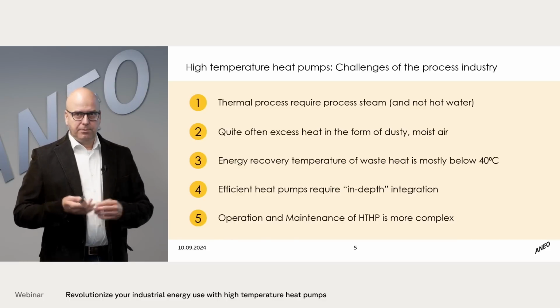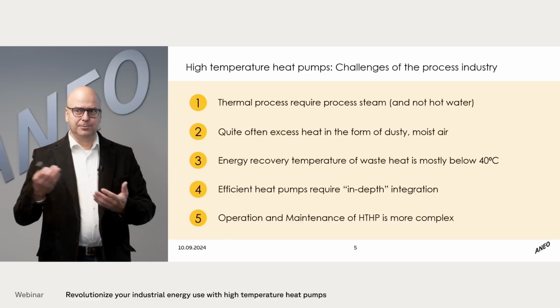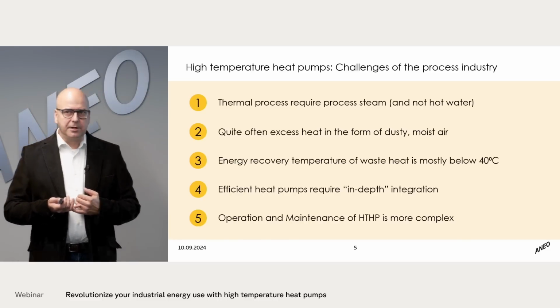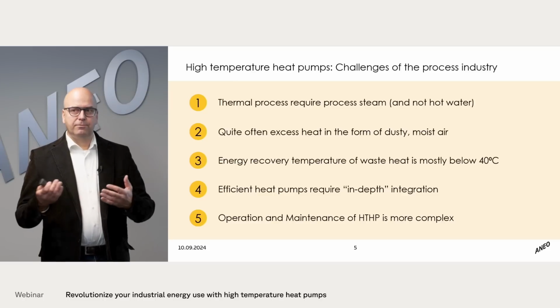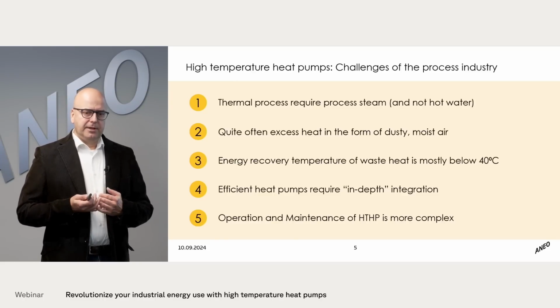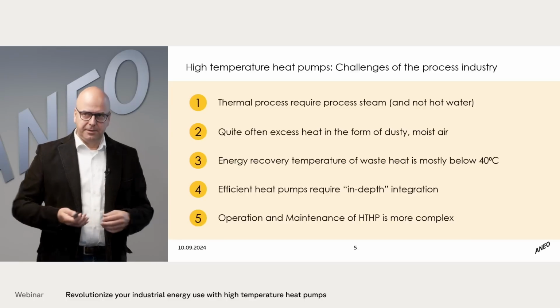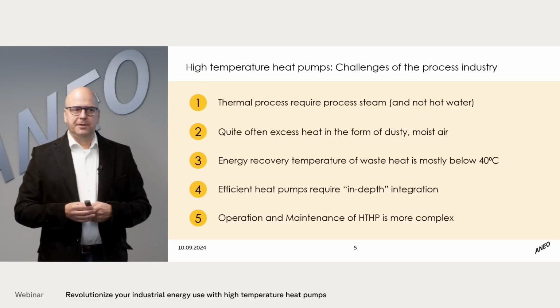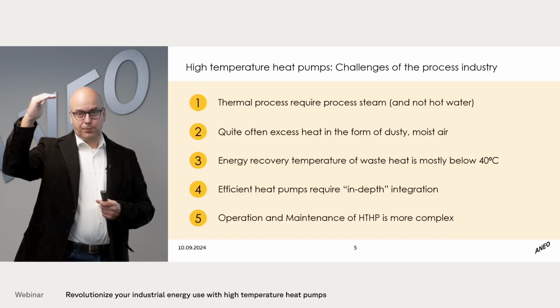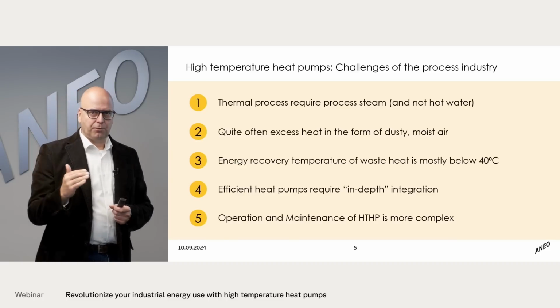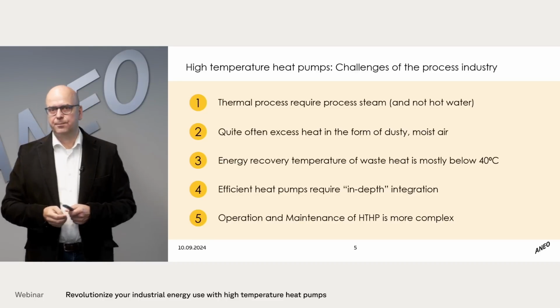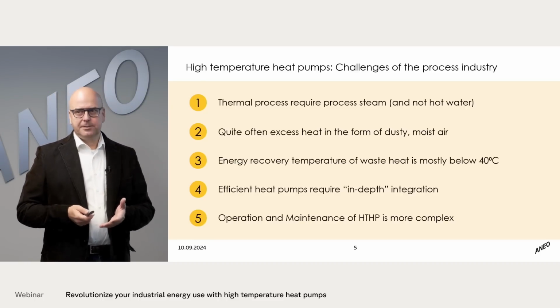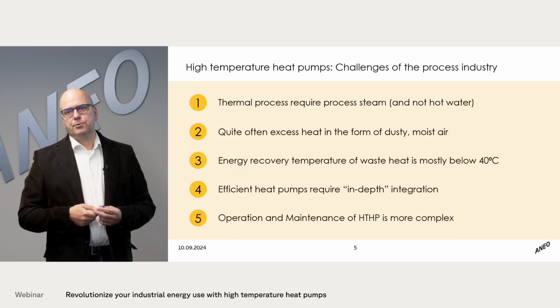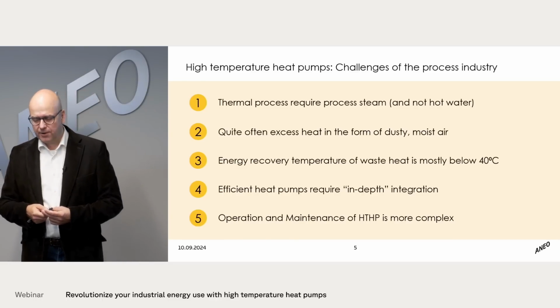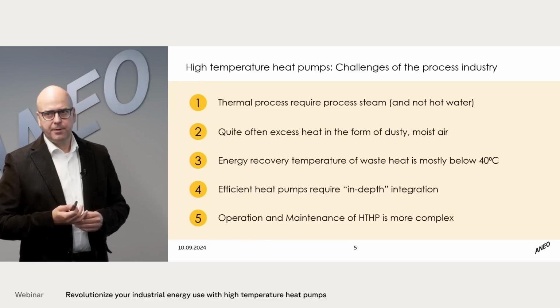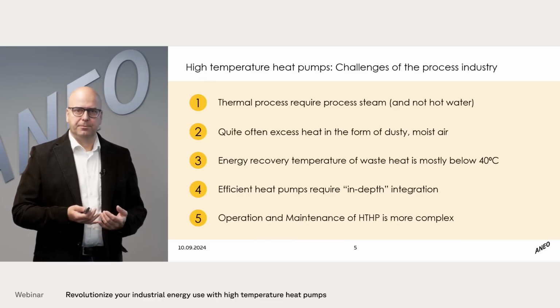By doing this setup, recovering excess heat, especially when it's sensible as well as latent, we see that the real energy recovery temperatures for the industry are normally below 40 degrees. I'm quite frequently confronted with cases where they say, we have 70, 80 degrees waste heat. But when we look at the case in detail, we see you have maybe 1 kilowatt at 70 degrees, and then you start to cool down your waste heat stream. In order to get out 1 or 2 megawatt, we need to cool it down to 40 or 30 degrees. So if we want to get out a significant amount of waste heat, we need to cool it down below 40 degrees in most cases. That also means we have a high temperature lift to cover, so we need an efficient heat pump system, which requires this in-depth integration, as I have outlined before.